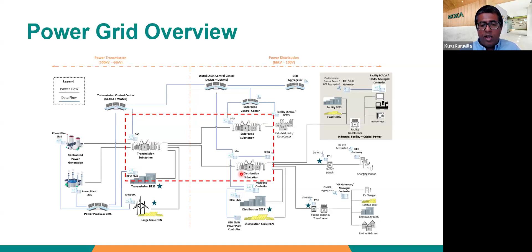So if you think about substation automation, there are a lot of different pieces of equipment being monitored. Not everything has the same priority in terms of data collection, communication, and storage. On one end, think about transformers - you typically monitor them for their life, things like temperature monitoring, the state of oil, and so on. That's important, but from a communication standpoint it doesn't have to be real time or urgent.